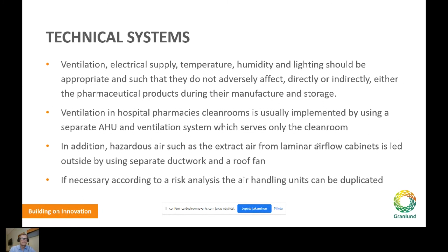Air exchange rates are normally between 15 to 50 air changes per hour in rooms, so B areas have the biggest air change rate. Supply air is brought to the room through ceiling diffusers which are equipped with HEPA filters, and the extract air is removed from the room by floor level extract grills on the walls. Normally the circulation air rate is about 80 to 90% of supply air, but if there are for example BSL areas, then there is no recirculation air, so all must be fresh air.